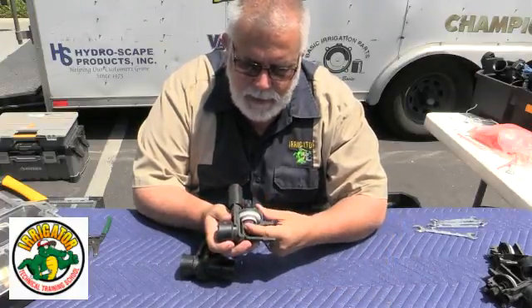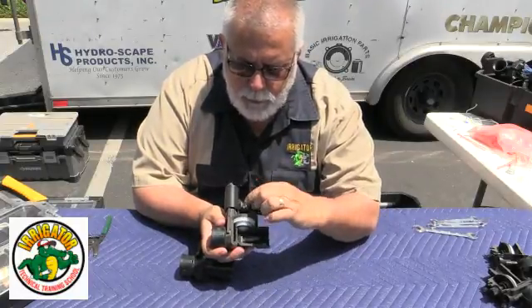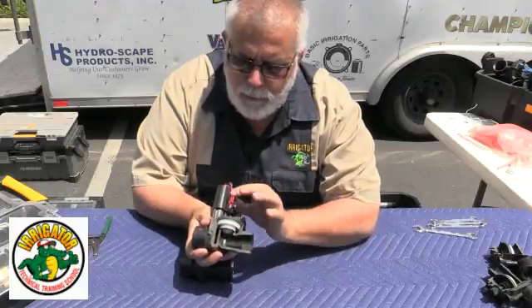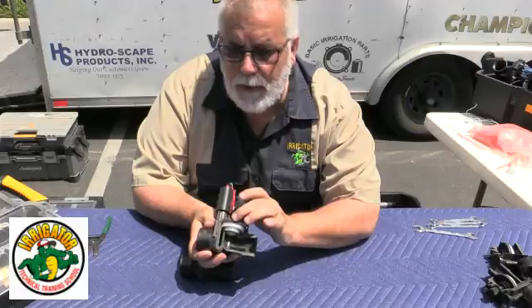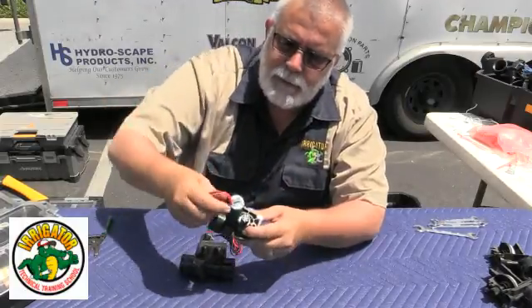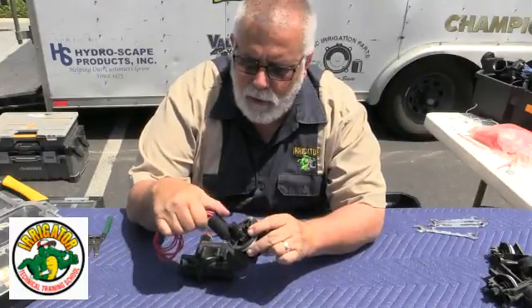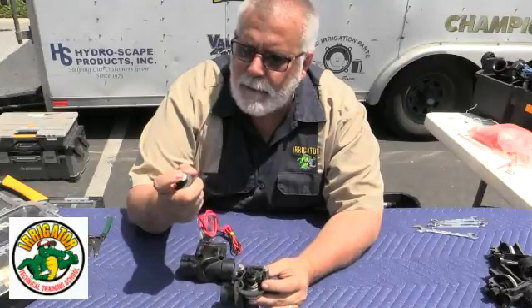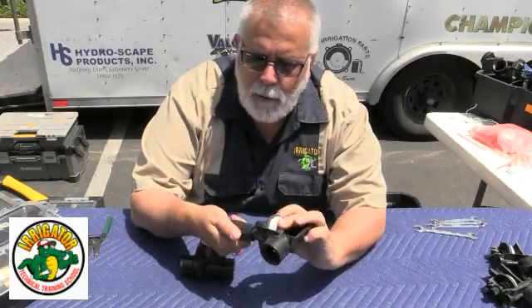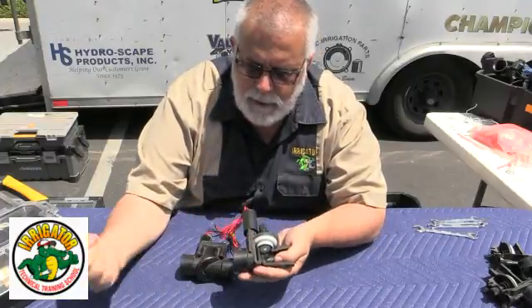I put my finger in and I can touch the diaphragm. So the water goes up the center and pressurizes the upper part of the bonnet. Then when the solenoid opens up, or the bleed screw, it takes the water up off of the upper part of the body. All I've got to do is turn this — as you can see here, it says manual on or off. I open this, it lifts the plunger right here, and then it makes the valve open. It drops back down and the valve is closed.